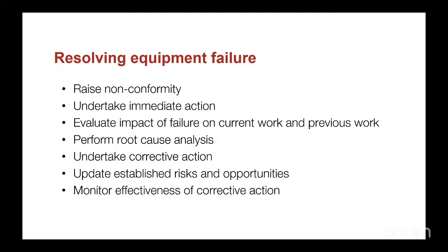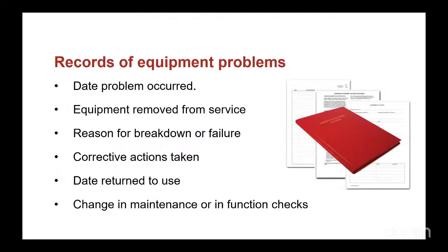Now, there's an error. You have to raise a non-conformity. You have to take immediate action. You have to evaluate the impact of that failure. You have to do a root cause analysis. So the success of the root cause analysis is to give you an understanding of what should be the corrective action. If the root cause analysis is not properly done, then the corrective actions will not be effective. So you have to also monitor for the effectiveness of that corrective action.